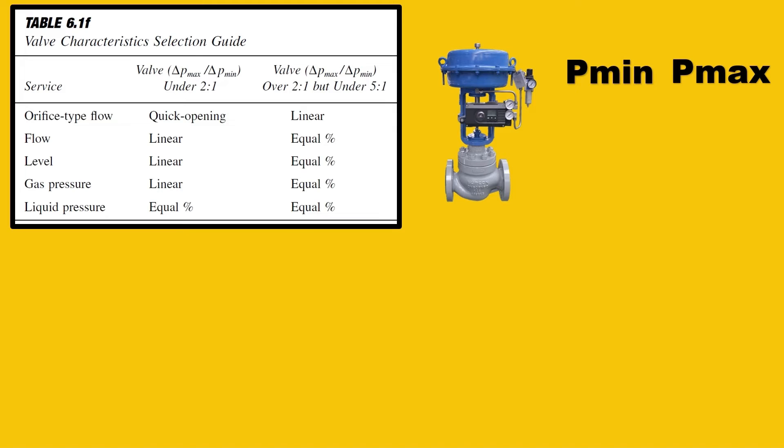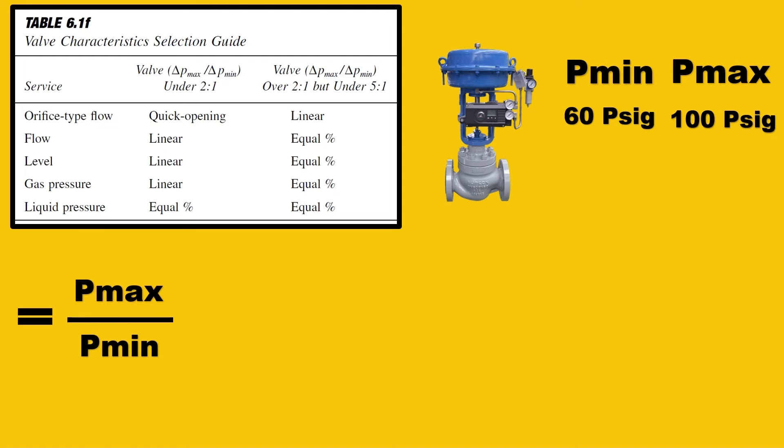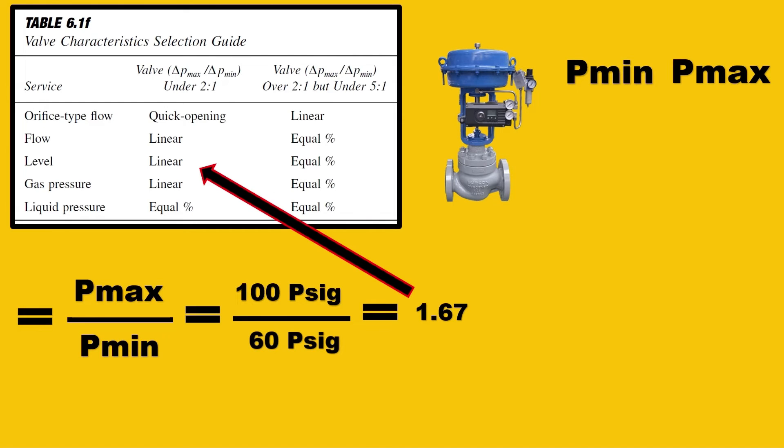Imagine you have a valve with minimum pressure 60 psig and maximum pressure 100 psig. The formula is simple: Pmax/Pmin = 100/60 = 1.67. The pressure variation is less, so it recommends going for linear characteristics.